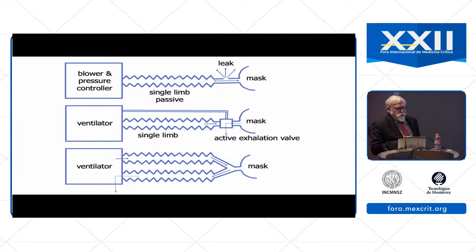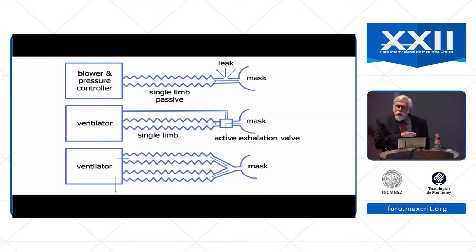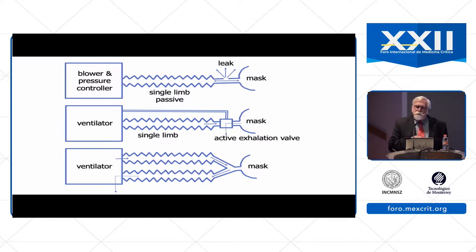If we look at the circuit used for non-invasive ventilation, there are fundamentally three types of different circuits that might be used. One might use a single limb passive circuit, as illustrated here. With this type of circuit and ventilator, it is important that there is a leak port incorporated into the circuit. That leak port can either be in the circuit near the mask, or in some applications, the leak port is within the mask itself.